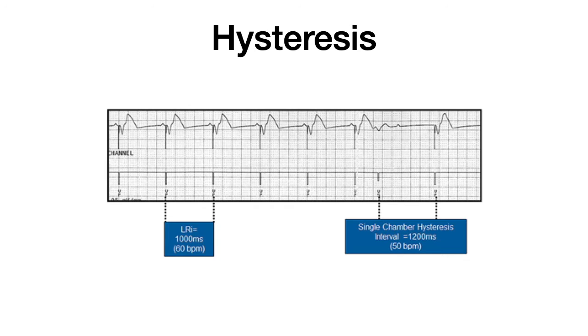Programming the hysteresis function on in the pacemaker will allow the prolongation of the first pacemaker escape interval after a sensed event. So a pacemaker programmed at a cycle length of 1000 milliseconds and a hysteresis of 1200 milliseconds will allow 200 milliseconds more for another sensed QRS to happen. If another QRS complex is not sensed, then the pacemaker will continuously stimulate the heart at the programmed rate of 60 beats per minute or 1000 milliseconds. This will occur until a second sensed event happens, and this will restart the timing cycles again.